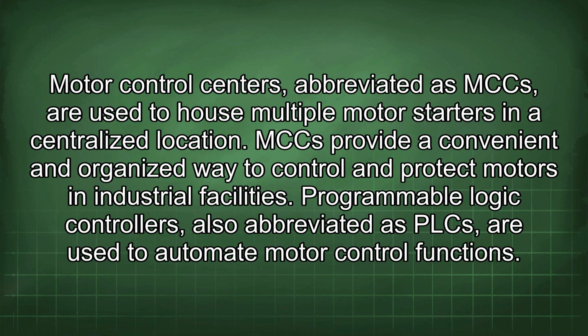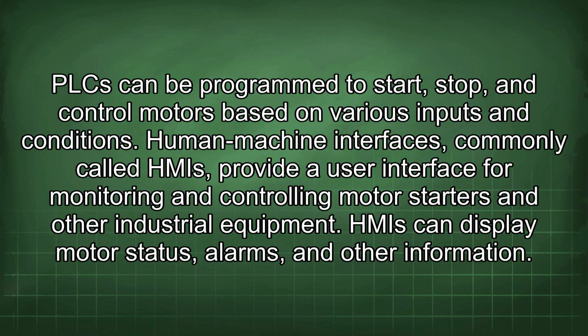Motor control centers, abbreviated as MCC, are used to house multiple motor starters in a centralized location. MCC provide a convenient and organized way to control and protect motors in industrial facilities. Programmable logic controllers, also abbreviated as PLC, are used to automate motor control functions. PLC can be programmed to start, stop, and control motors based on various inputs and conditions. Human-machine interfaces, commonly called HMI, provide a user interface for monitoring and controlling motor starters and other industrial equipment. HMI can display motor status, alarms, and other information.